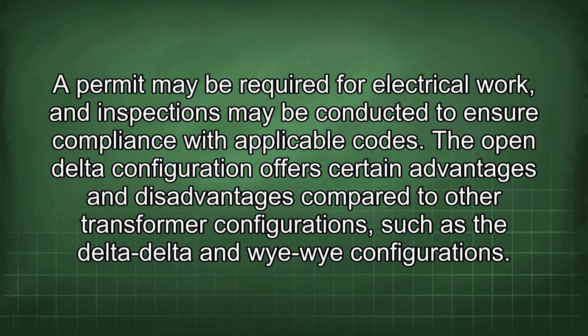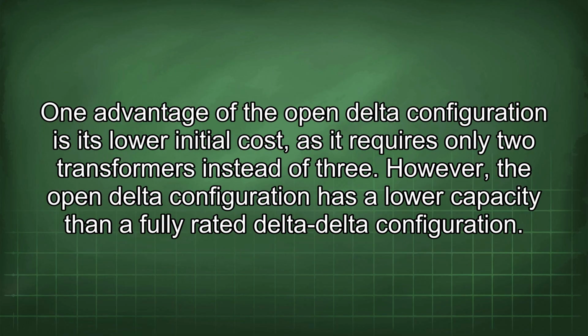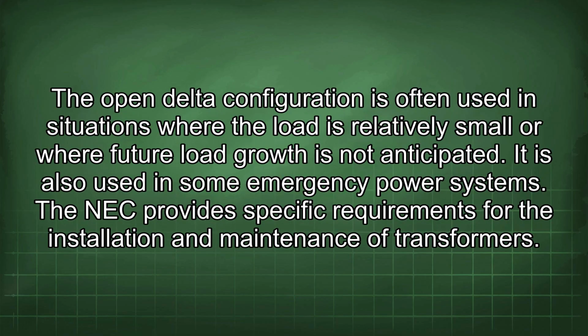The open delta configuration offers certain advantages and disadvantages compared to other transformer configurations, such as the delta-delta and Y-Y configurations. One advantage of the open delta configuration is its lower initial cost, as it requires only 2 transformers instead of 3. However, the open delta configuration has a lower capacity than a fully rated delta-delta configuration. The open delta configuration is often used in situations where the load is relatively small or where future load growth is not anticipated. It is also used in some emergency power systems.